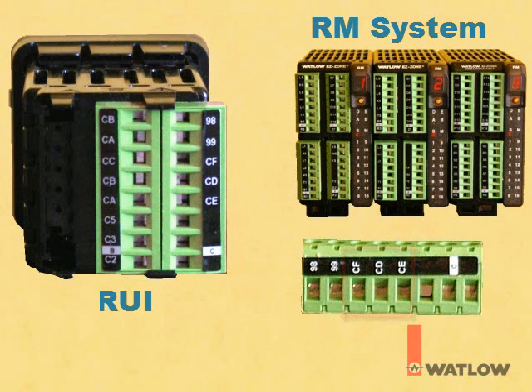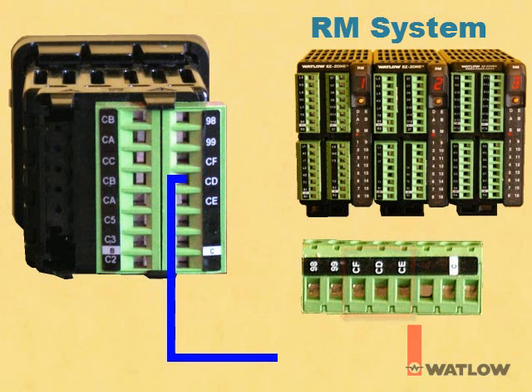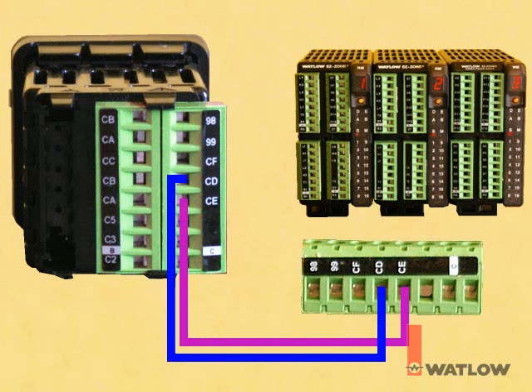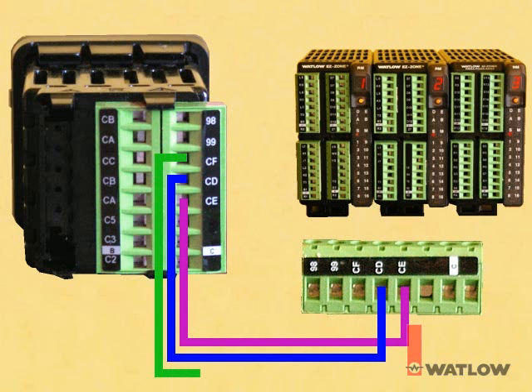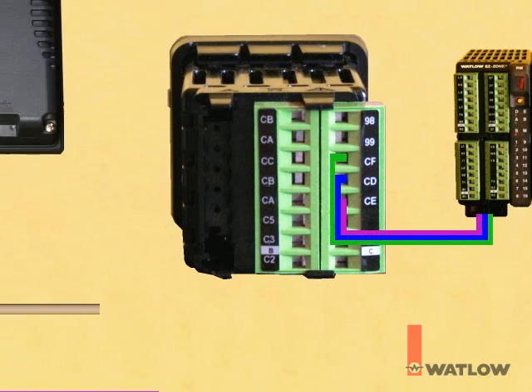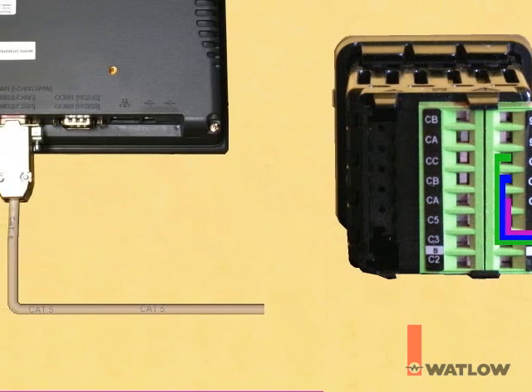connect the standard bus terminals on the RUI with the corresponding terminals on one of the RM modules. With one pair, connect CD on the RUI to CD on the RM, and CE on the RUI to CE on the RM. And with one wire from another pair, connect CF on the RUI to CF on the RM.